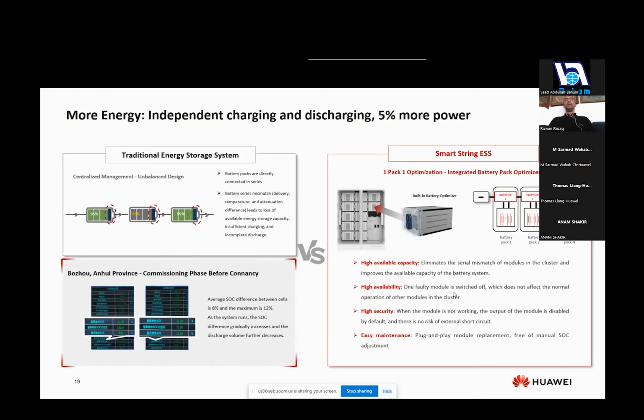So with that optimizer built inside each battery pack itself, we are able to ensure that the charging and discharging is done independently to each battery pack in order for the higher security, easier maintenance, and available capacity can be fully charged. Now, if we look at the traditional solution, when other battery packs are charged up, for example, at 95%, the others which are in the same series will then be limited, which is not utilizing your complete offering of batteries.